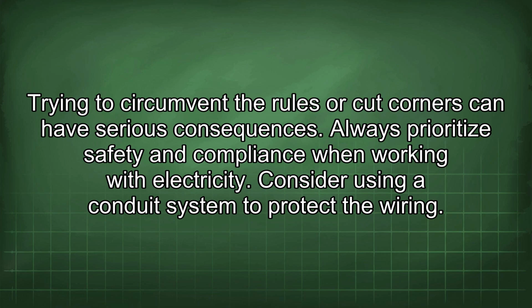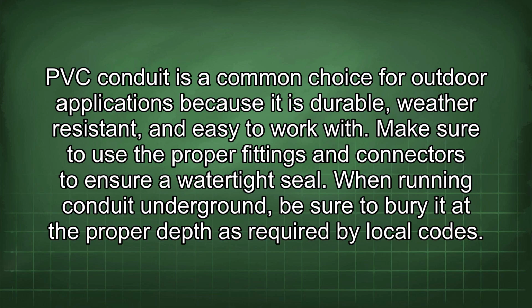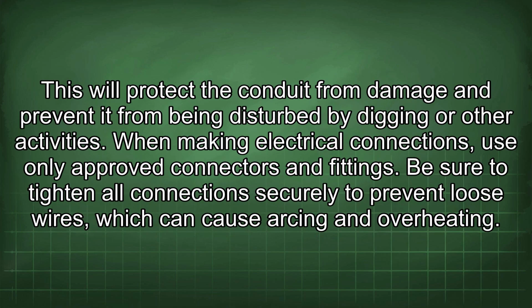Consider using a conduit system to protect the wiring. PVC conduit is a common choice for outdoor applications because it is durable, weather-resistant, and easy to work with. Make sure to use the proper fittings and connectors to ensure a watertight seal. When running conduit underground, be sure to bury it at the proper depth as required by local codes. This will protect the conduit from damage and prevent it from being disturbed by digging or other activities.